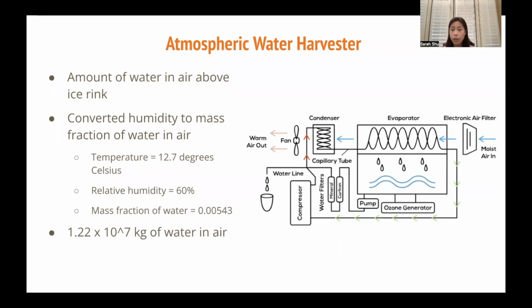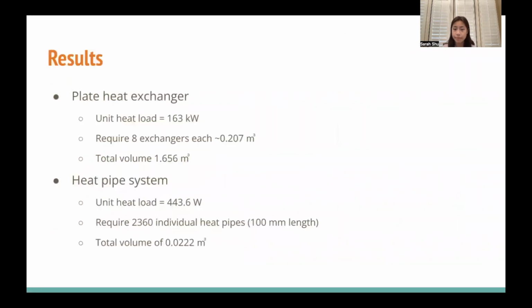For the atmospheric water harvester, the amount of water above the ice rink was calculated by converting humidity to mass fraction of water in the air. This ensures that the air is saturated with enough water to be drawn by the device. The results of the calculations indicated that the plate heat exchanger had a unit heat load of 163 kilowatts, requiring 8 exchangers. The total volume for the plate heat exchanger was approximately 1.6 meters cubed.